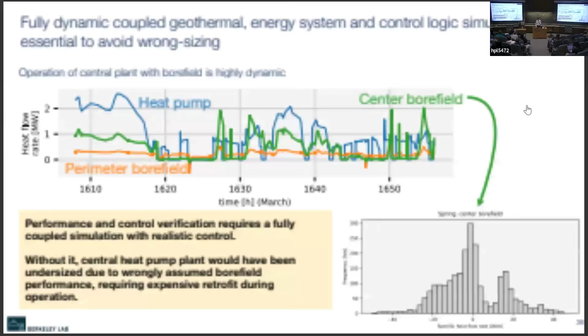On the bore field performance, I mentioned earlier that it was essential to couple the bore field model with the mechanical system and the control. Just looking at the 2 days of operation here, and the heat flow rate between the heat pump in the central plant and then the bore fields.